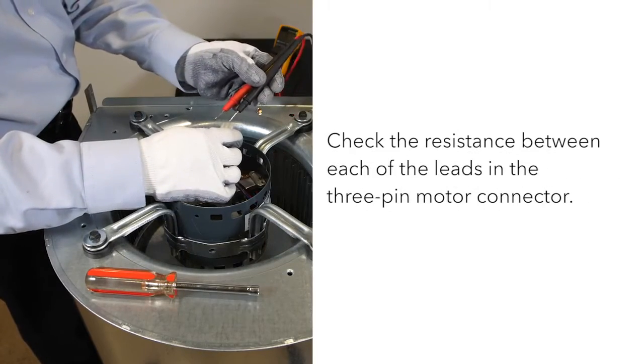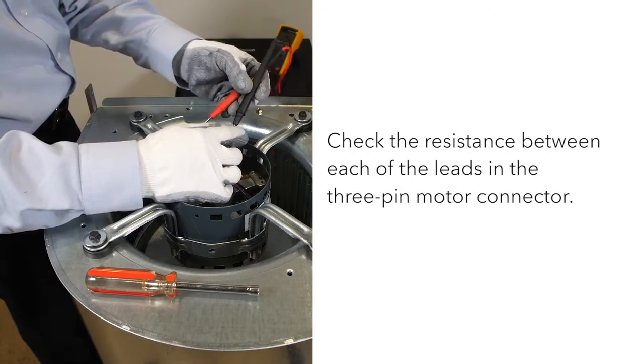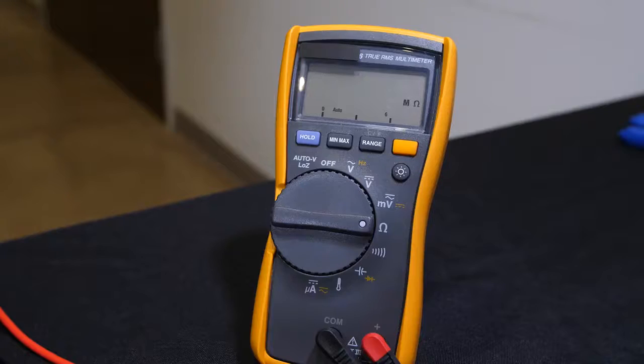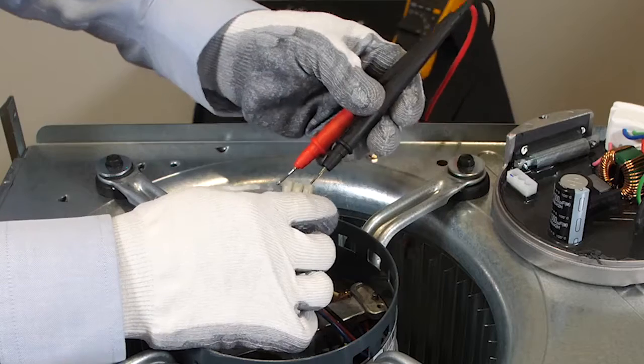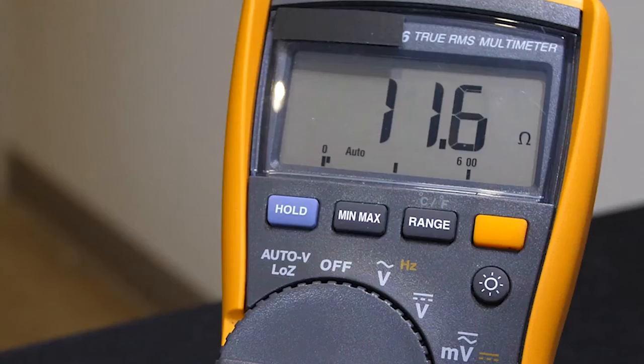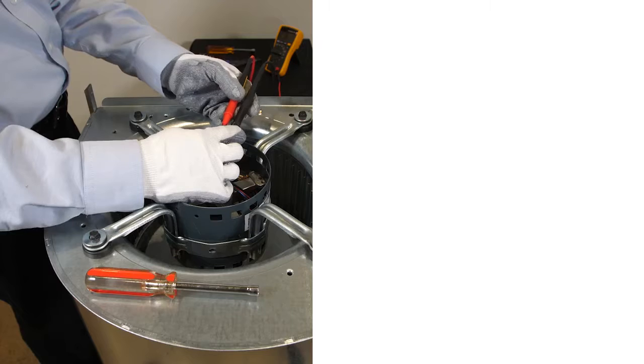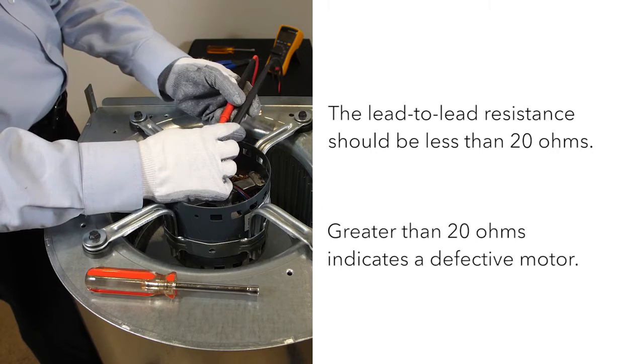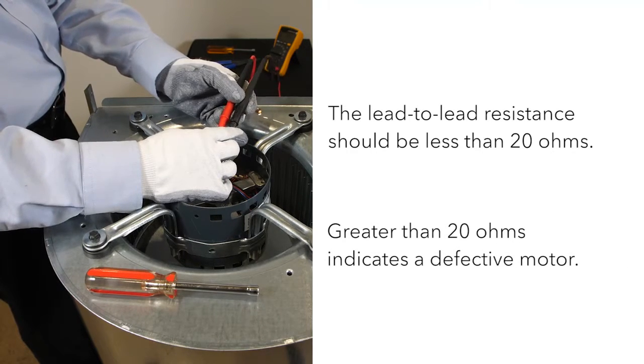Check the resistance between phase to phase by checking between each of the leads in the three-pin motor connector. The lead to lead resistance across any two leads should be less than 20 ohms and each lead to lead resistance should be the same within plus or minus 10%. If this test fails and you have greater than 20 ohms, it means you have a defective motor and it needs to be replaced.